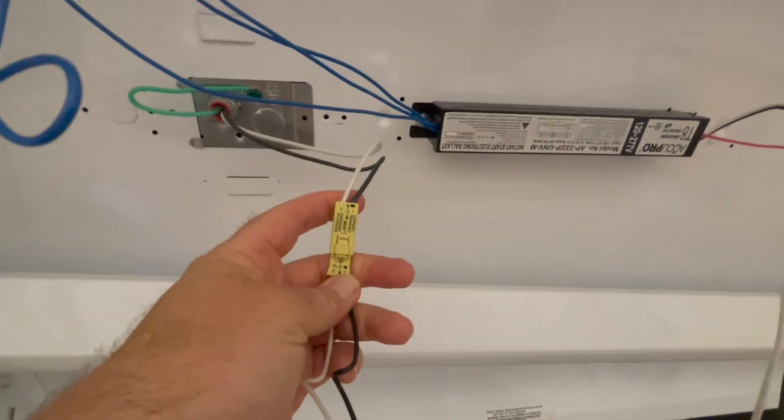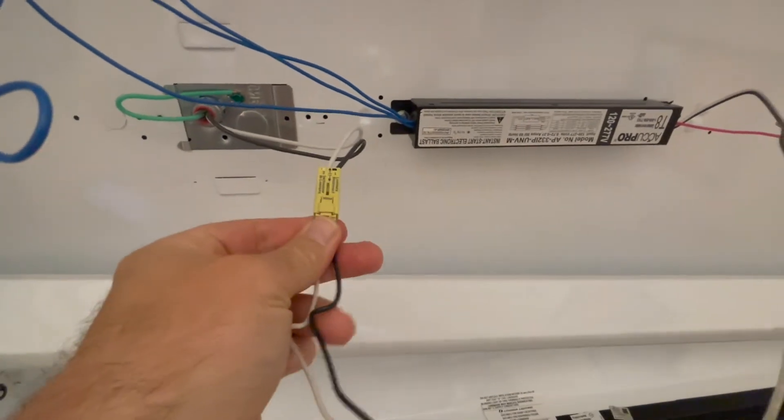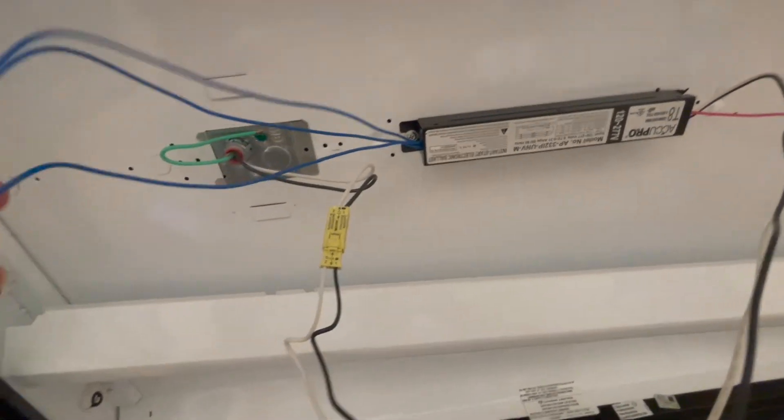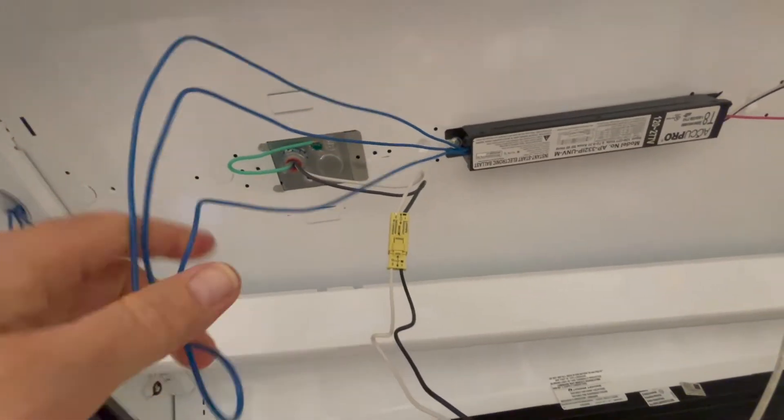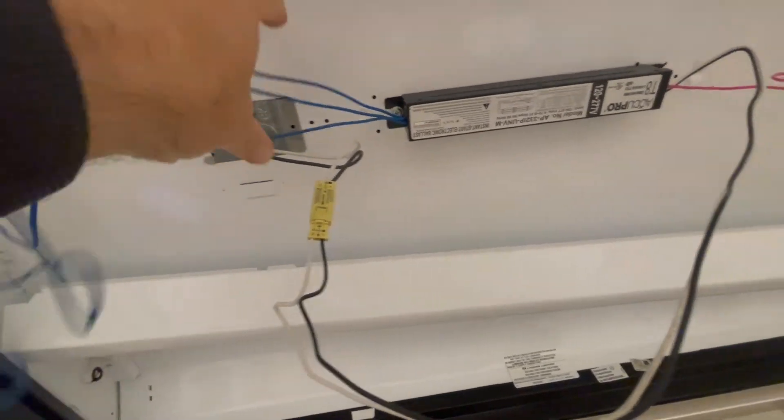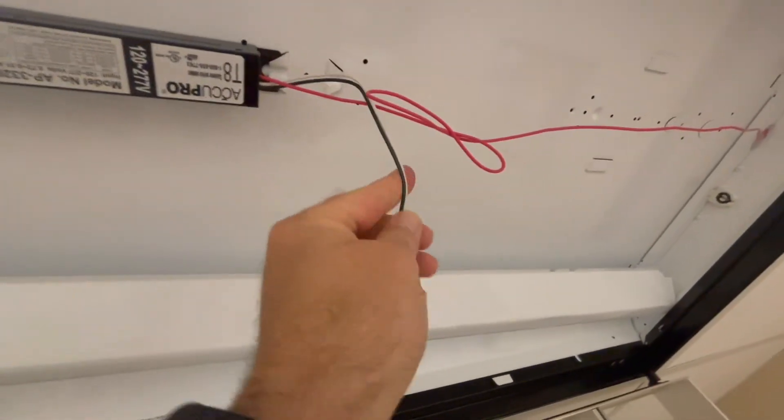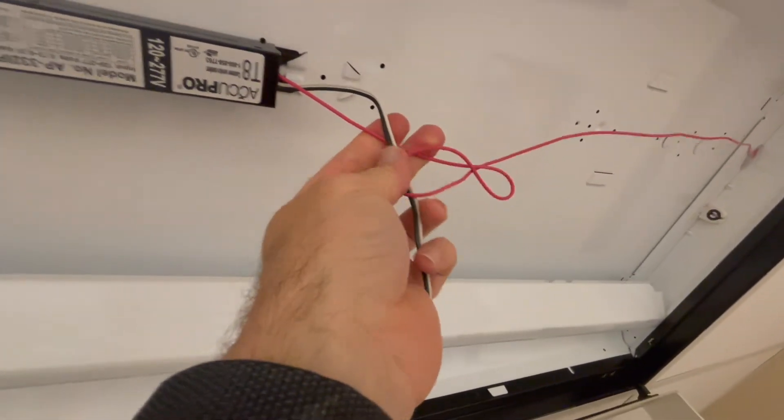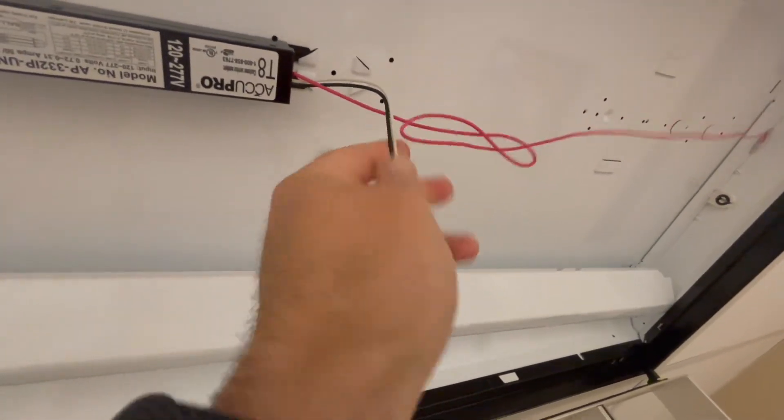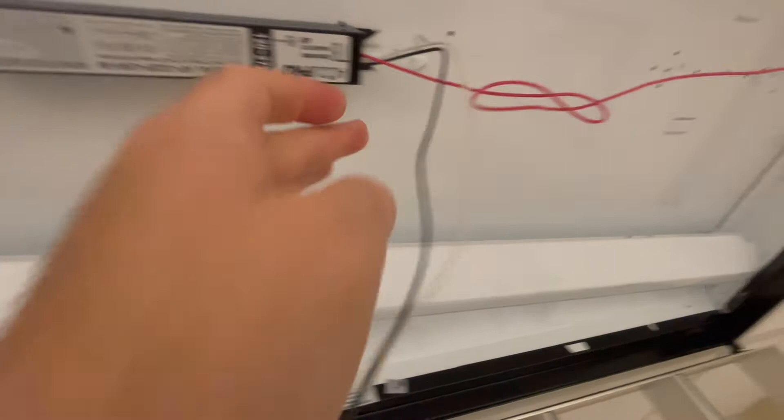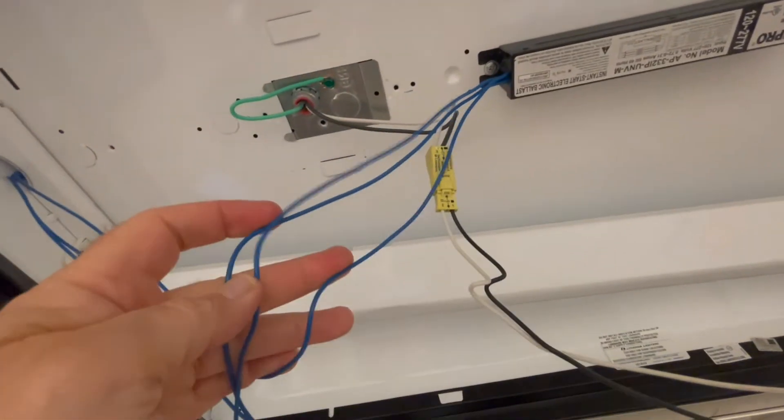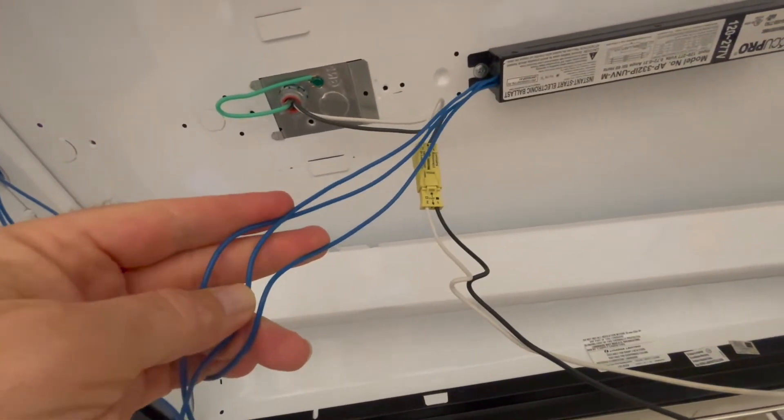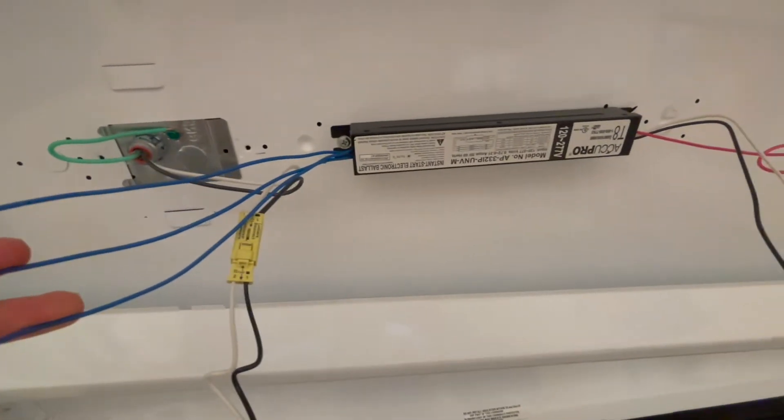You're going to unfasten this, and once the power is disconnected, I want to clip the blue wires up here around the ballast, clip the load wires around here and the red wire. Then I'm going to wire the white wire to the red and wire the black wire into all three of the blue wires.